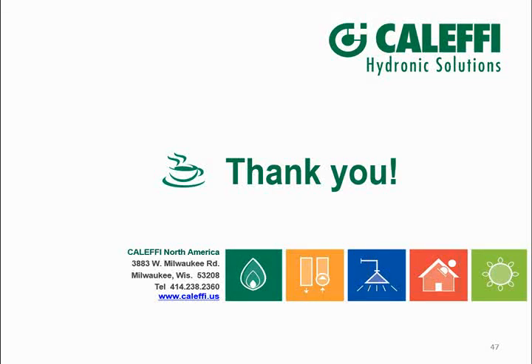Most of your tank manufacturers will, based on the run of the pipe and the size of the tank, make a recommendation. The thing is, you don't have a very high flow rate through there. We're talking for a 100-gallon system, a little bit over 2 gallons that are moving, and it's a slow process as the water expands. So the pipe size does matter, but I'd say in most cases it's going to be maybe 1/2 inch to maybe 3/4 inch, but the tank manufacturers will also list in their literature what that pipe size should be.